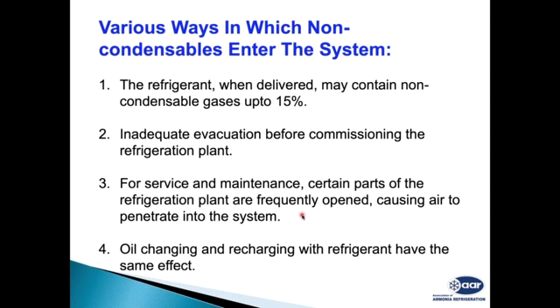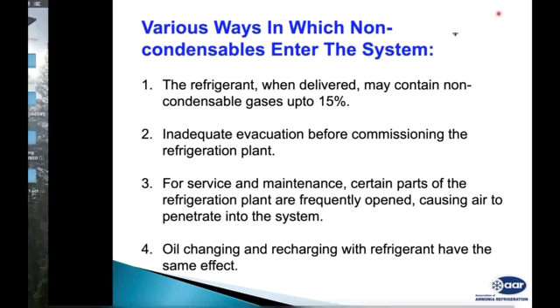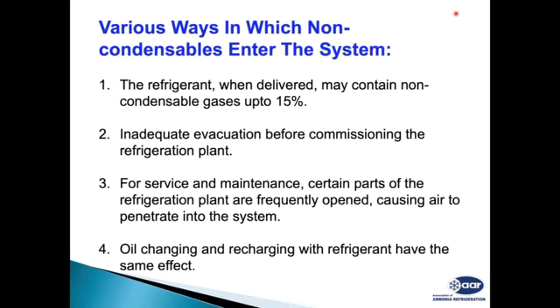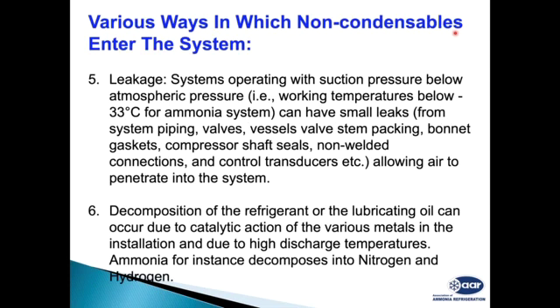Many times when our refrigerant does not have a purity certificate, it contains non-condensable gases, air. And then, when our plant is installed and we are pressure testing, when proper evacuation is not done, proper vacuuming not done, or after the pressure testing, when for servicing and maintenance we open any parts of the system, there is a possibility of this air entering into the system. Then when we are charging ammonia, oil, or removing oil, we are opening a part of the system. There is always a possibility of air entering into the system.